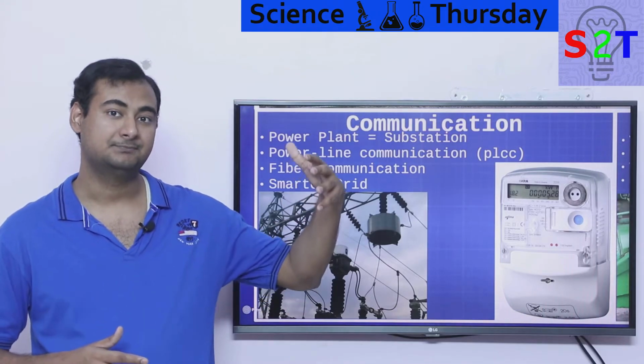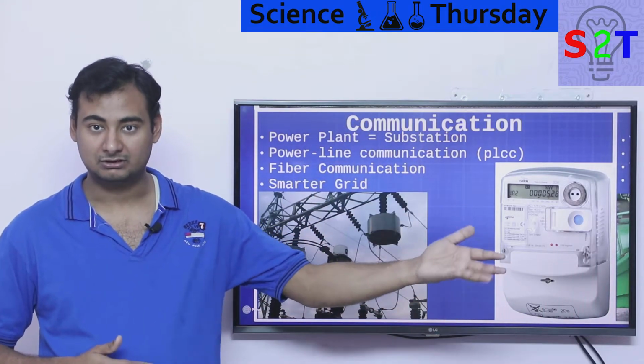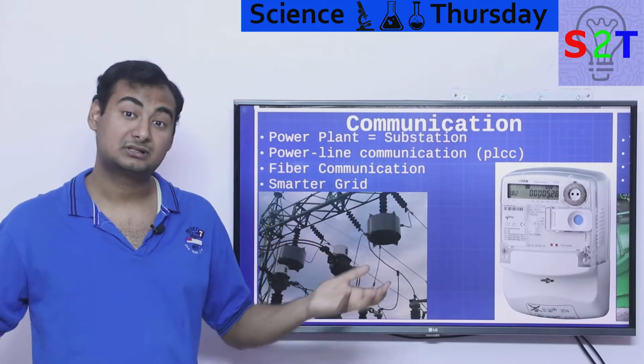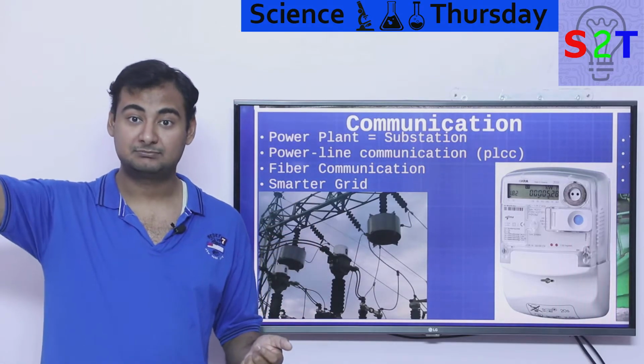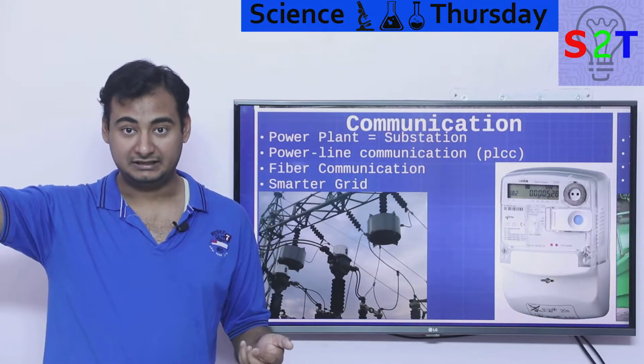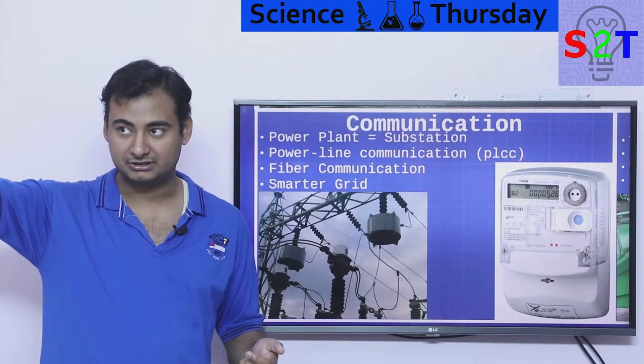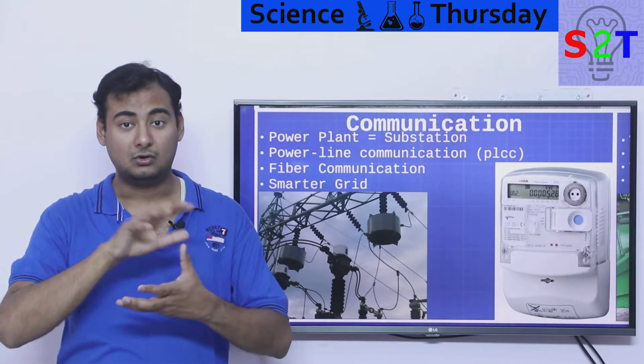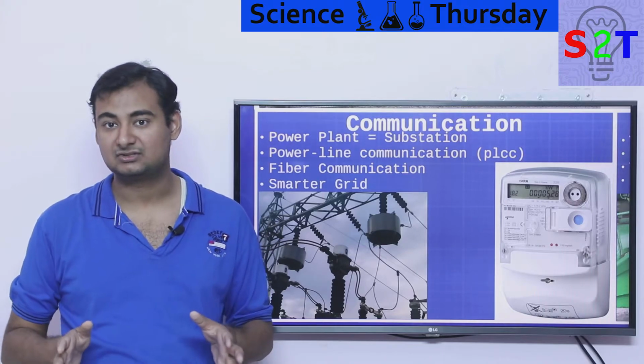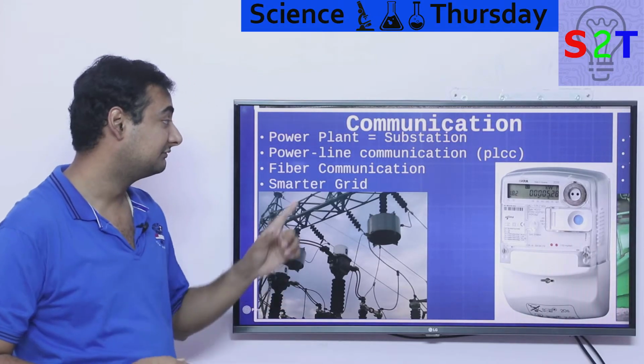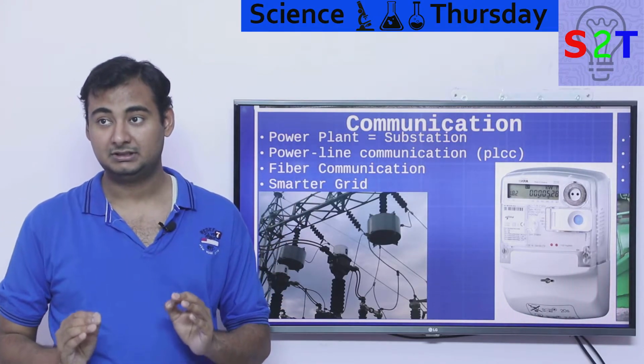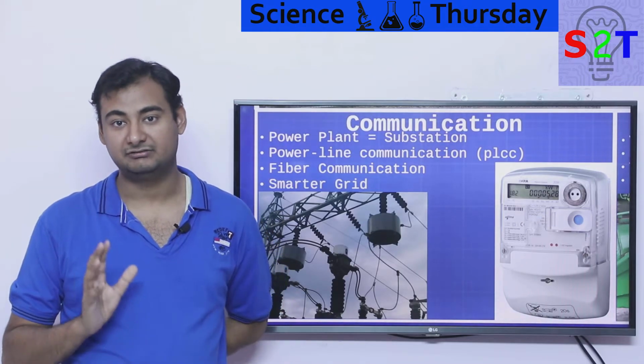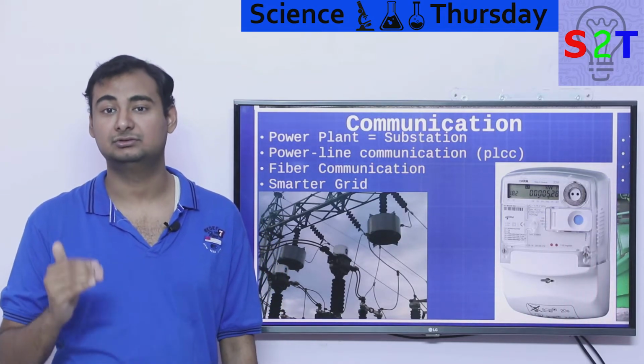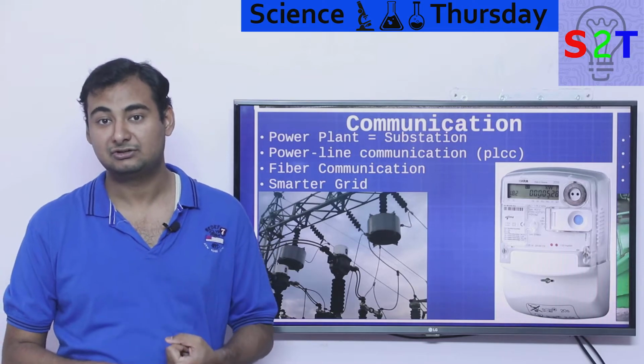This allows, say, if a 500 megawatt plant is overloaded and has to cut power, but you're communicating with others, you might find another power plant is overproducing by 100 and has to tone down. Rather than toning it down, you say, okay, sell that electricity here. All this trading that goes on is almost like a stock market, happening because of communication. So communication is crucial. You cannot have a national grid without communication; you must have good communication. Without communication, you cannot maintain your frequency.